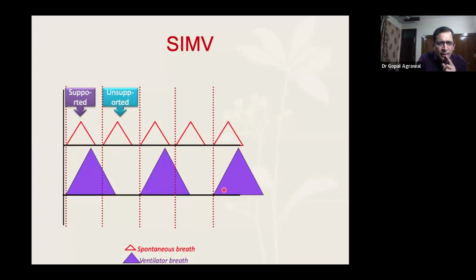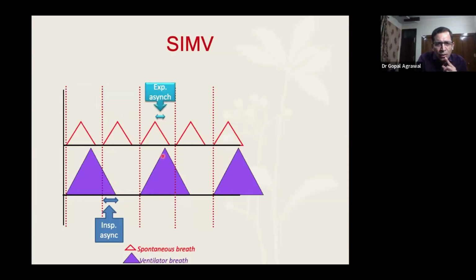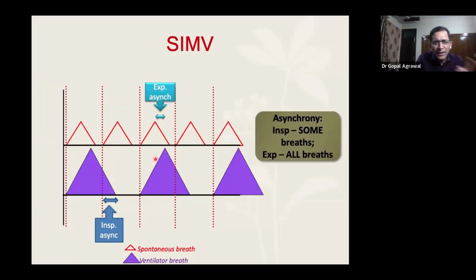Let's see how it's better than IMV in terms of synchrony. Because the baby is already in inspiration mode and the machine is not detecting that breath, this is inspiratory asynchrony. The baby is inspiring, but the machine is not detecting that. That's inspiratory asynchrony. Baby is in exhalation mode, machine is still giving inspiration. So expiratory asynchrony. So it is better than IMV because some breaths are synchronized, not all breaths. So inspiration is synchronized somewhat, but expiration is not synchronized. This is a disadvantage of SIMV.